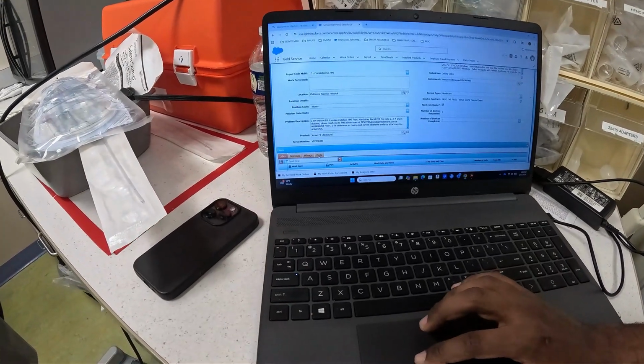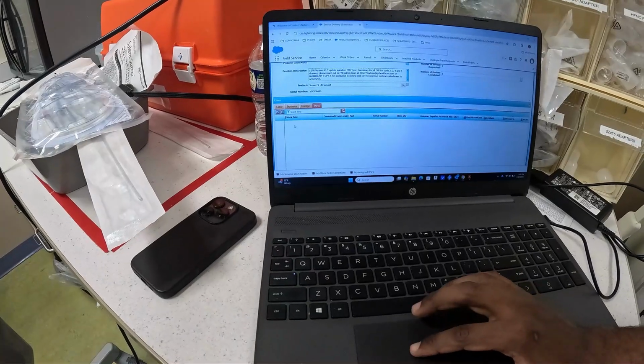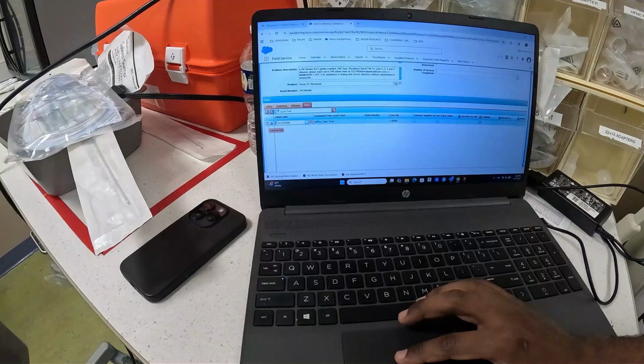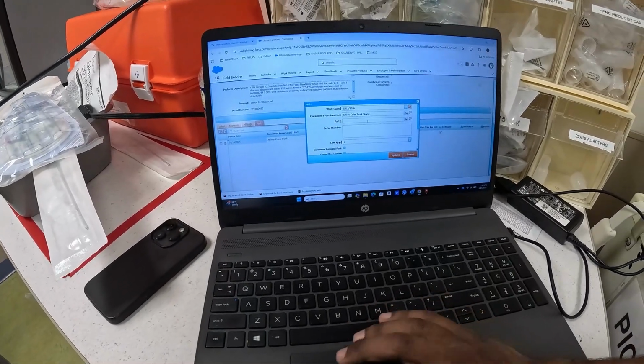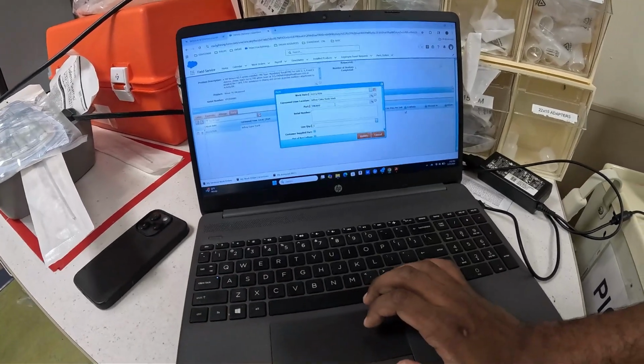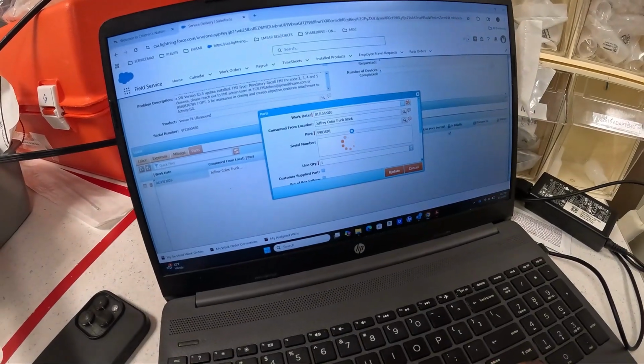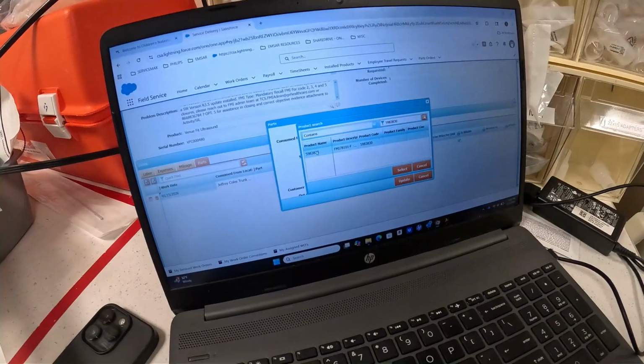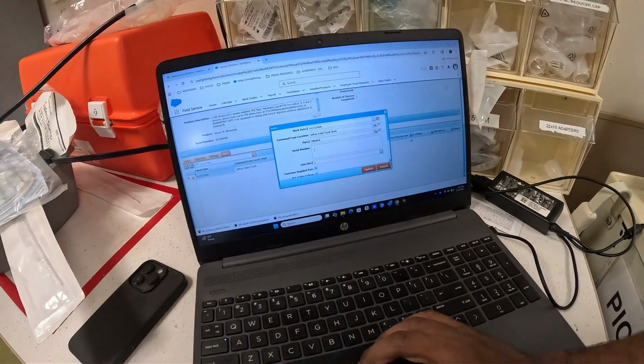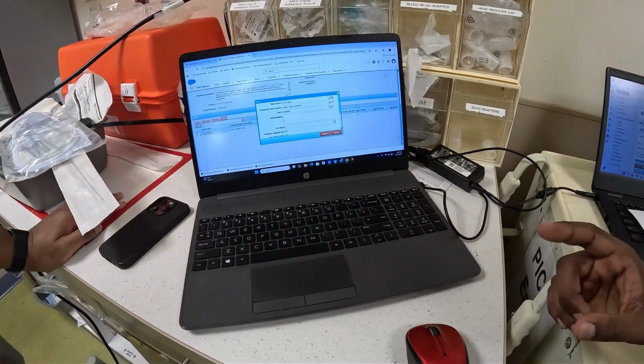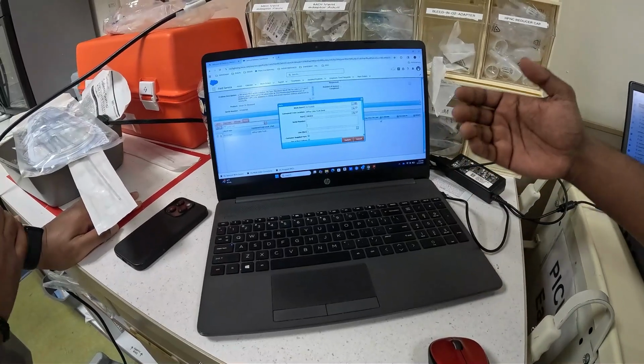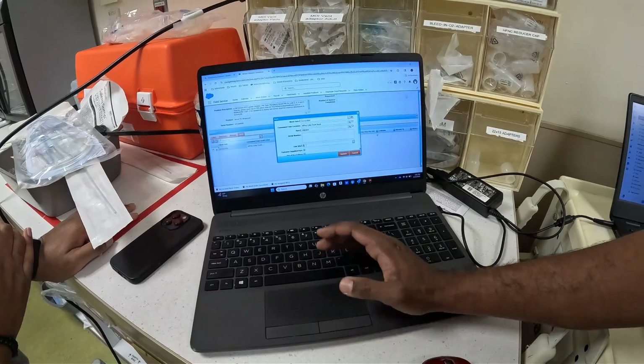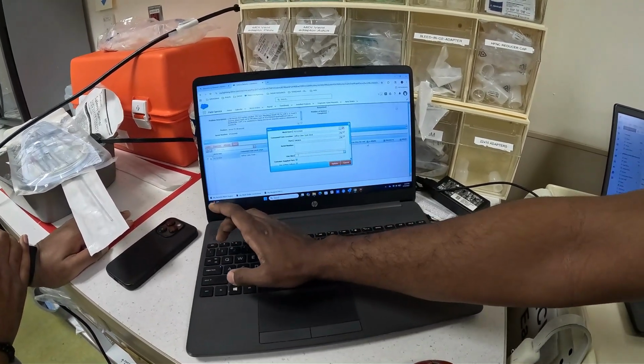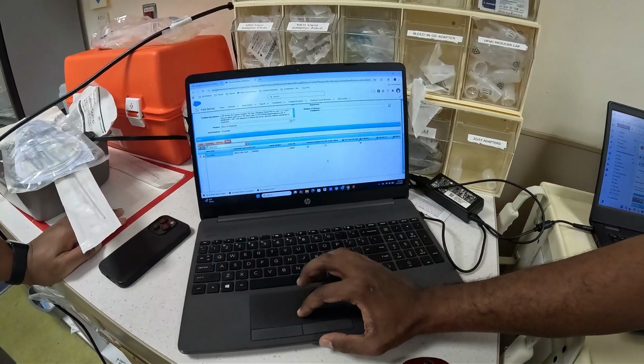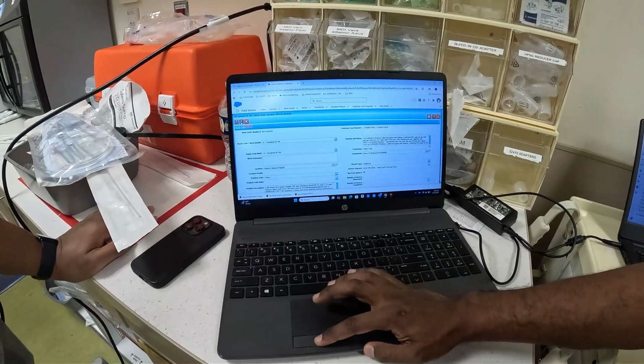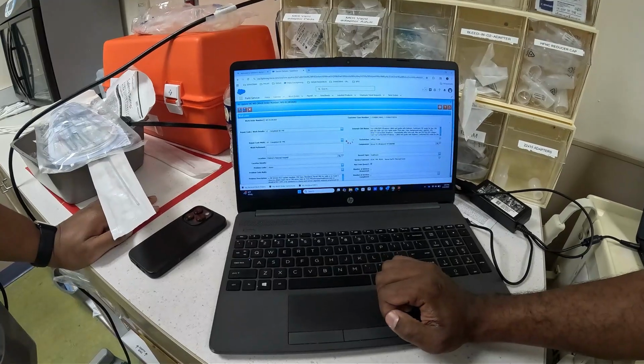come down to the parts section, and you'd add a line. Now you would go into this line and you would paste that number and you press enter. And you click on this right here. Nice. Now, for the Venue Fit, you would only need to change out one battery, which is what my colleague did here for this work order. But for the Venue Go, you would have to put down 2 for this. But since this was a Venue Fit work order, you put down 1 and you update the work order. And you come up here and you do a quick save so it populates. Okay.